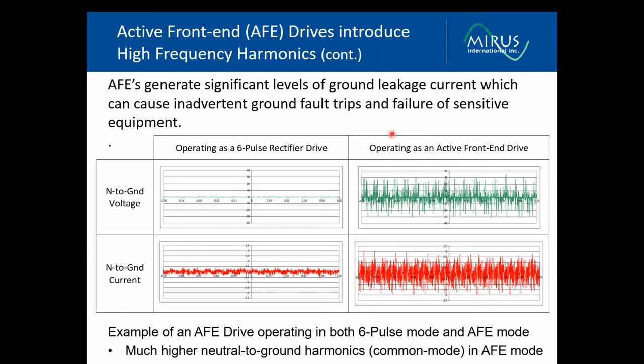It also introduces ground leakage currents as a result of neutral to ground voltages or common mode voltages. So here's, again, operating as a standard six pulse drive, very little neutral to ground voltage introduced by the drive, very high levels introduced when it's operating as an active front end drive. The neutral to ground current, you can see as an active front end drive, much, much higher levels of ground currents, which circulate through the electrical system and can cause all kinds of different problems with sensitive connected equipment.